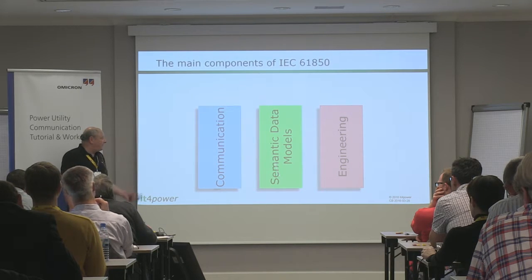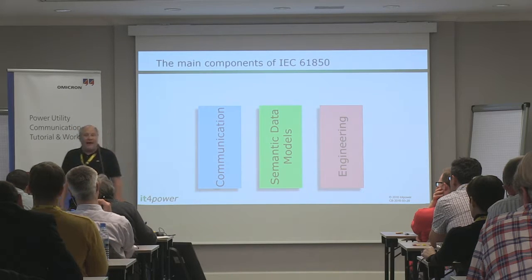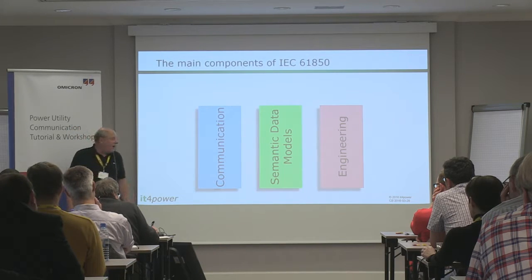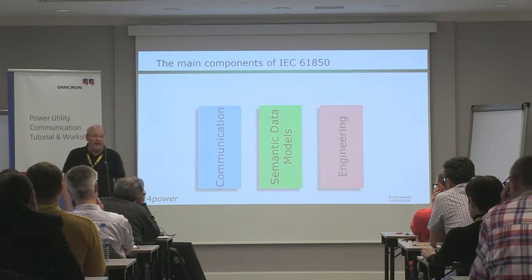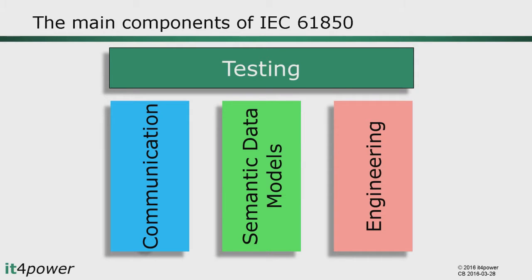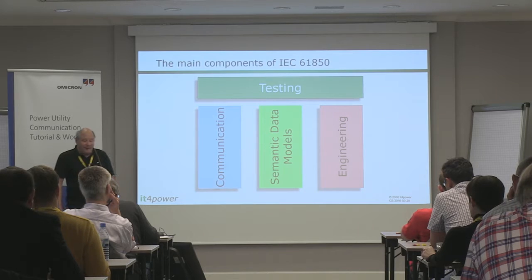61850 of course deals with communication, but it also includes the definition of semantic data models. It not only covers how you transmit information from A to B, but also what exactly that information is — defining semantic objects and data structures used in the power world. The third key element is the complete engineering process behind 61850, which allows automated configuration of your system with different tools talking to each other, and also enables automated testing. On top of these three elements, the standard includes specifications for conformance testing of components developed for 61850.